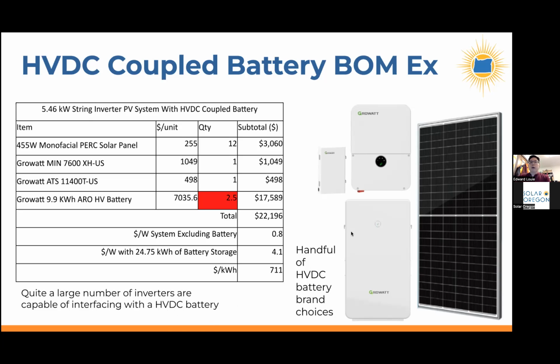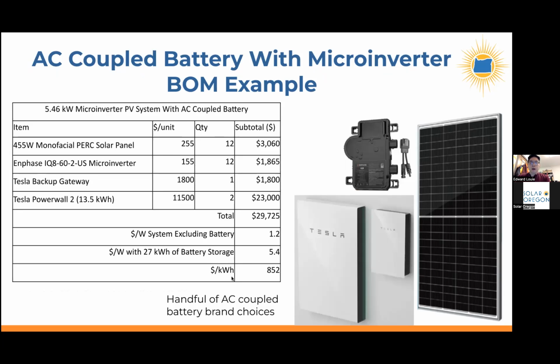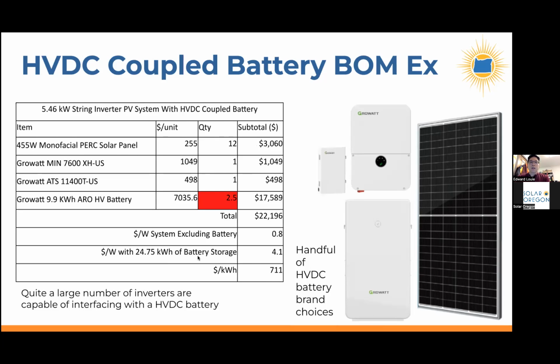Because high voltage DC batteries do not have an inverter that converts AC to DC and DC back to AC, they have a smaller bill of materials. So logically, the battery would cost a little bit less. And do we see that to be true? Yes. The dollar per kilowatt hour for the battery in the Tesla Powerwall is about $852, and the high voltage DC battery is only $711. So yes, we see that reflected in the price of the batteries. By having a smaller bill of materials, they are a little bit less expensive.